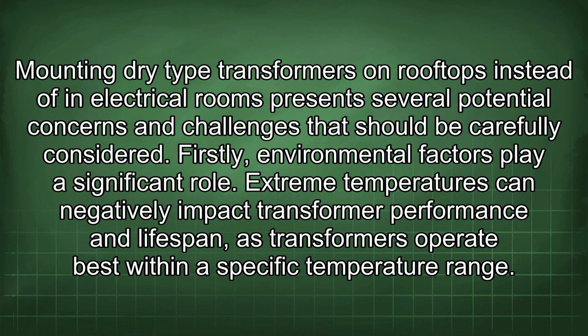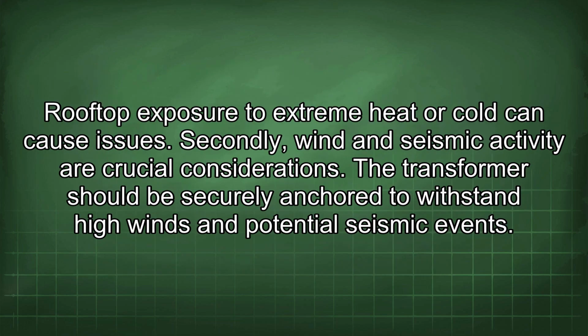Mounting dry-type transformers on rooftops instead of in electrical rooms presents several potential concerns and challenges that should be carefully considered. Firstly, environmental factors play a significant role. Extreme temperatures can negatively impact transformer performance and lifespan, as transformers operate best within a specific temperature range. Rooftop exposure to extreme heat or cold can cause issues.